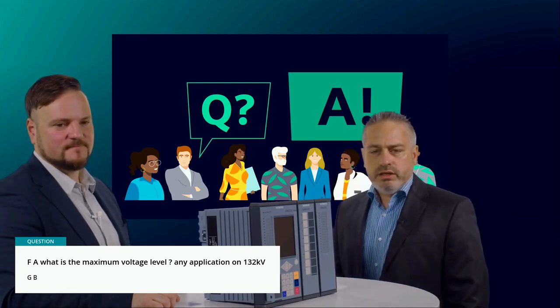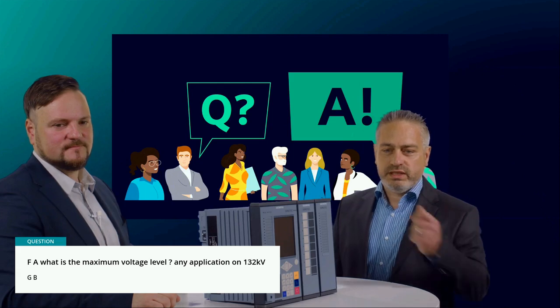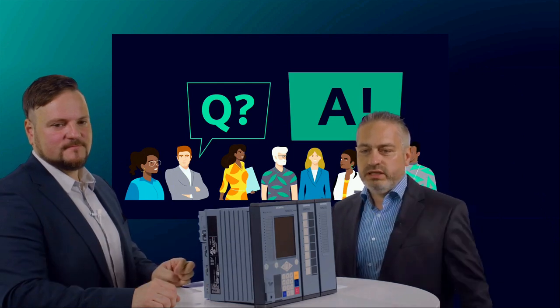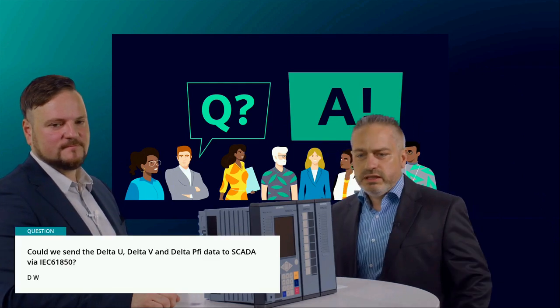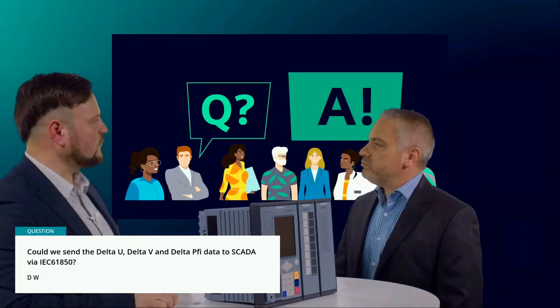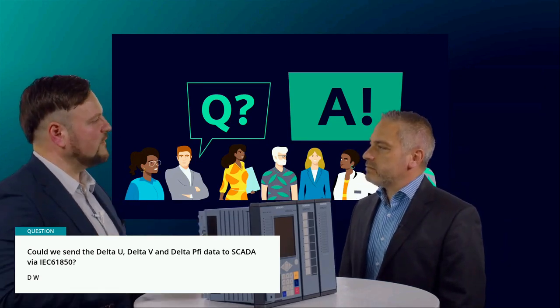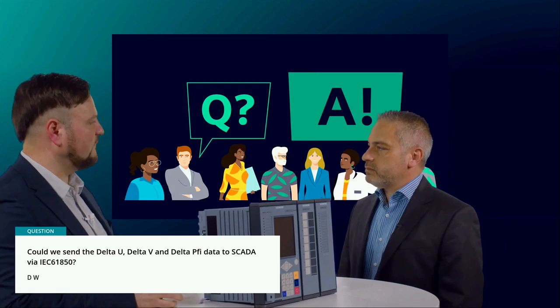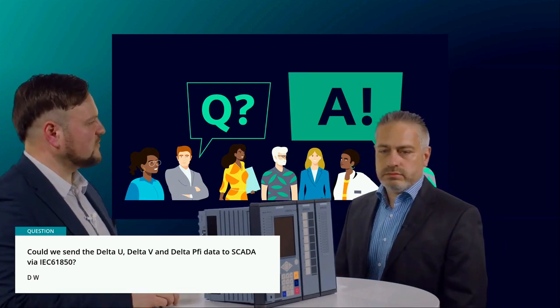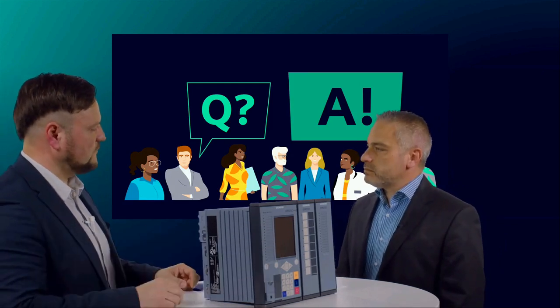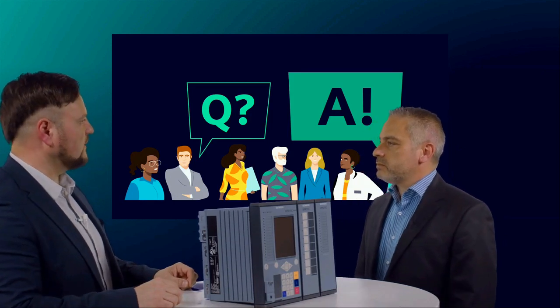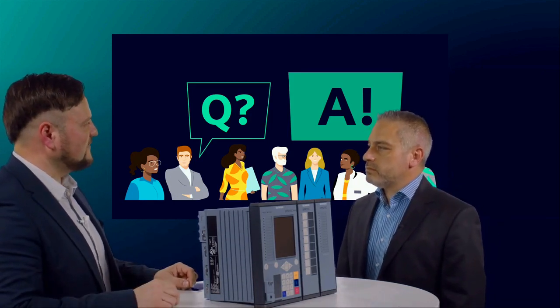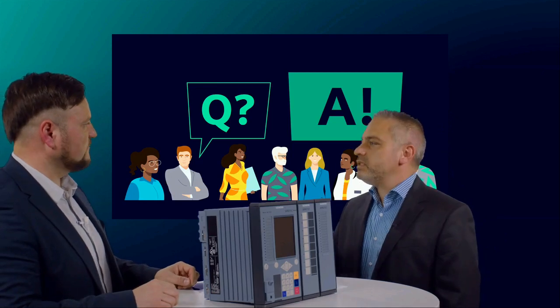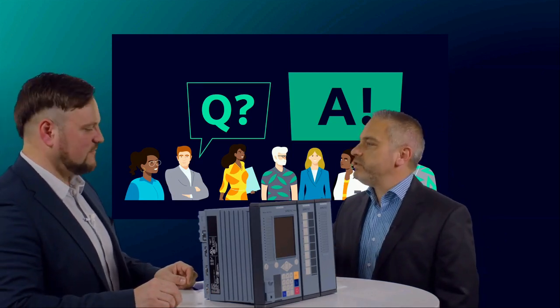Could we send delta U, delta V, and delta F to SCADA via IEC 61850? Yes, this is possible. During development, we keep an eye on all these measuring values - functional values are available. You can route these functional values to the communication port and then send all these values to the SCADA system. It's already included in the 61850 communication.